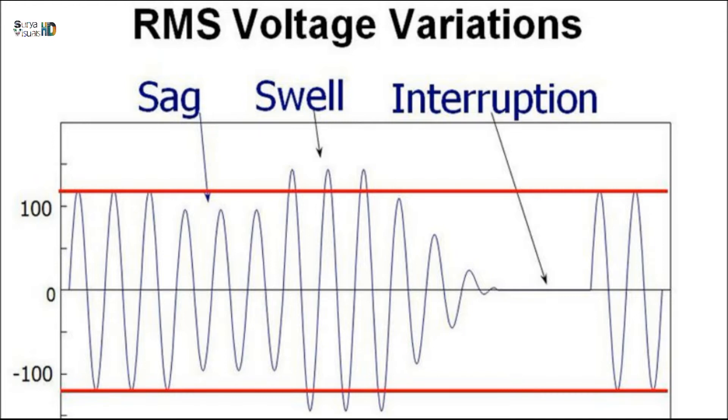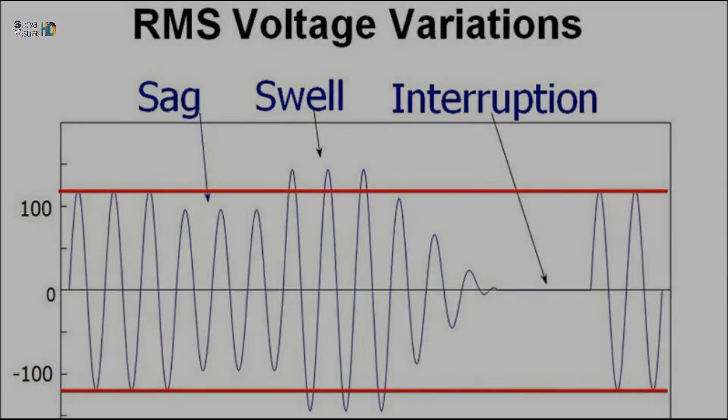A voltage sag is a short duration, typically 0.5 to 30 cycles, reduction in RMS voltage caused by faults on the power system and the starting of large loads such as motors.